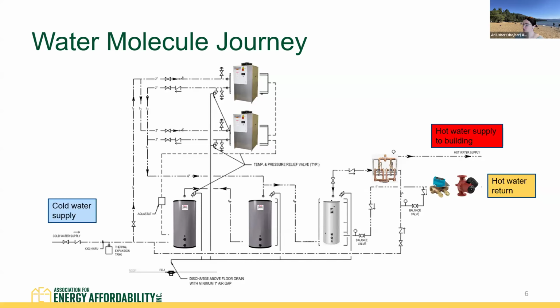When there's no demand on the system, there's also a water recirculation pump that runs to keep the piping primed with hot water. This is really a way to save water, because if those pipes were all full of cold water, the first person to turn on their shower in the morning would have to wait a long time to get hot water, and that's a lot of water down the drain. So we've got this important circulator pump, which is balanced with balancing valves here.